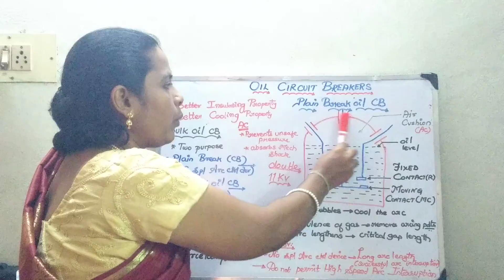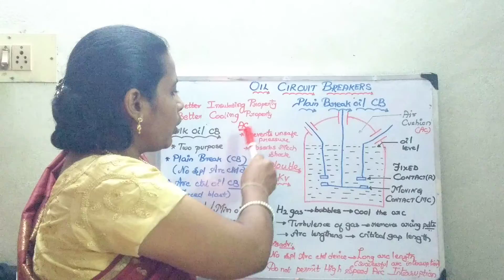The purpose of providing the air cushion is that whenever the arc is struck, the oil gets vaporized and forms bubbles. If the air cushion is not there, it might lead to the explosion of the dome. So, to prevent unsafe pressure inside the circuit breaker vessel, you use this air cushion. Moreover, it also absorbs the mechanical shock produced by the oil movement. Thus, the air cushion serves two purposes: it prevents unsafe pressure inside the dome and absorbs the mechanical shock.